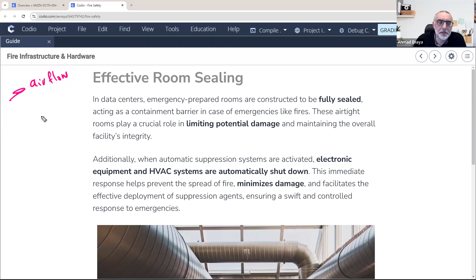Now, another technique that we should have in the data center is room sealing. Why do we need room sealing? Because fire actually spreads with airflow, mainly if we have airflow within the plenum and a lot of oxygen moving around, then this is the best circumstance for fire. If we have heat, fuel, and oxygen with airflow, this will cause the fire to move from one room to another. We want to control the fire. If this is our data center, we want to make sure that if there is any fire in any location, we want to control it. We want to seal that location from others.